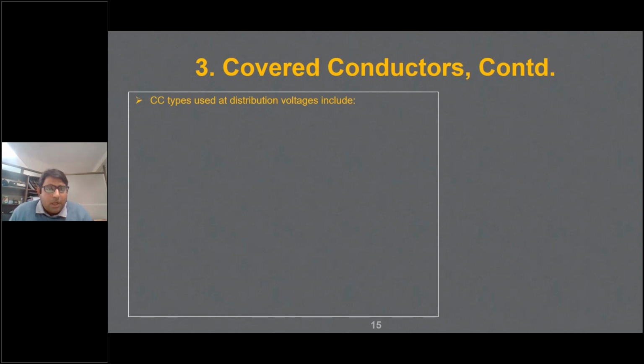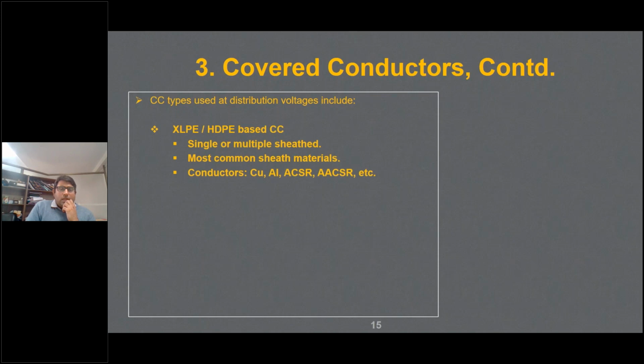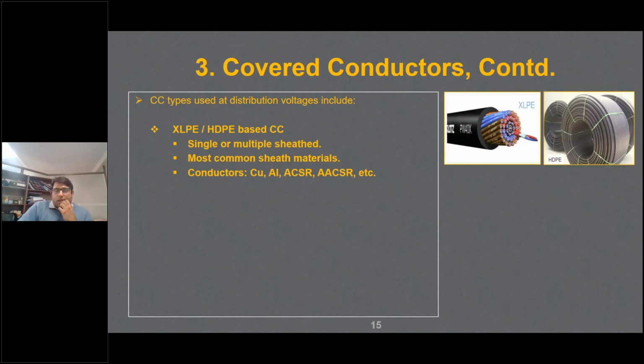So the covered conductor types at distribution voltages, the very first one is XLPE, or what we call cross-linked polyethylene, and high-density polyethylene. They may be single or multiple sheathed. These are the most common sheath materials in use today. And the conductors that are basically encapsulated by these kinds of materials are copper, aluminium, ACSR and AACSR, etc. As you can see on your right-hand side, both the XLPE, or cross-linked polyethylene, and high-density polyethylene conductors. Then we'll move to the next one.